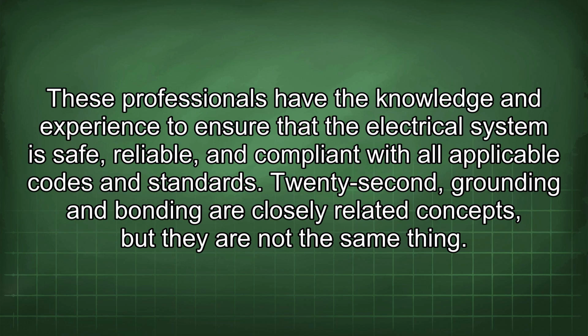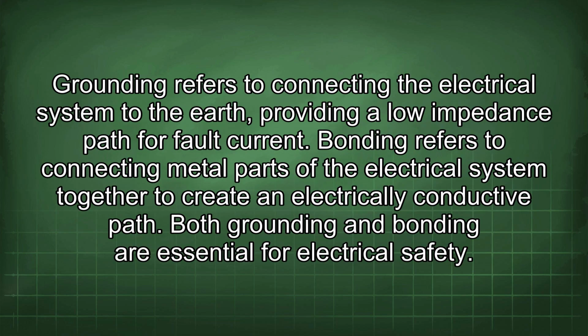22nd, grounding and bonding are closely related concepts, but they are not the same thing. Grounding refers to connecting the electrical system to the earth, providing a low impedance path for fault current. Bonding refers to connecting metal parts of the electrical system together to create an electrically conductive path. Both grounding and bonding are essential for electrical safety.